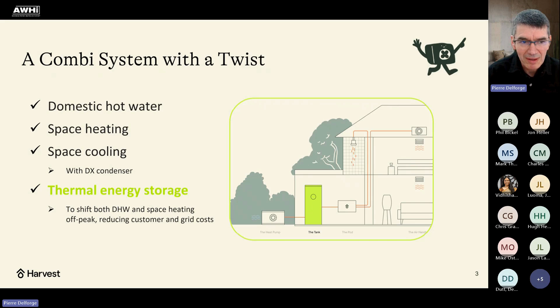And the harvest pod is where the magic happens. It's both a hydronic controller and an electronic controller. So from a hydronic perspective, think of a hydronic system, often installed in the basement. You're going to have on a wall somewhere pipes and pumps and valves and sensors, and it's pretty expensive to install because of all the site installation needs. So what we did is we integrated this in a box at the factory, tested at the factory, and plug and play on site to reduce installation costs and make it cost effective to install. So this is the basic of the hydronic system.